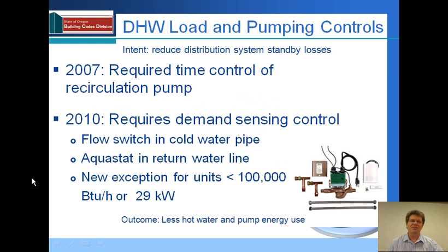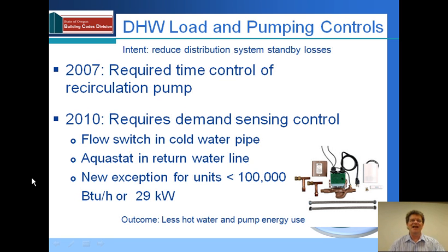Let's talk about that first case of domestic hot water. In this type of system, it's interesting that the heat lost from the piping that runs throughout the building can be significantly greater than the heat lost from the tank. As a result, the old code required time control of the recirculation pump so that at least after hours that pump was shut off. The primary savings here is not so much the pump energy, as these pumps are pretty small.